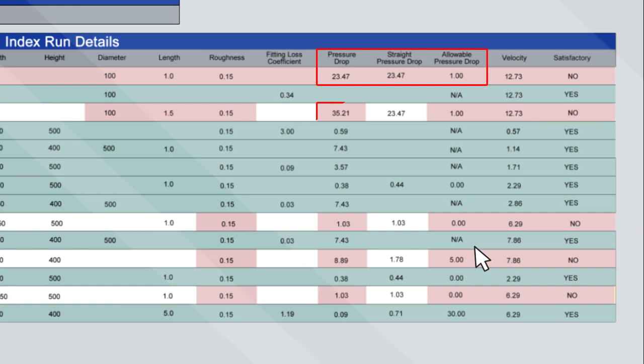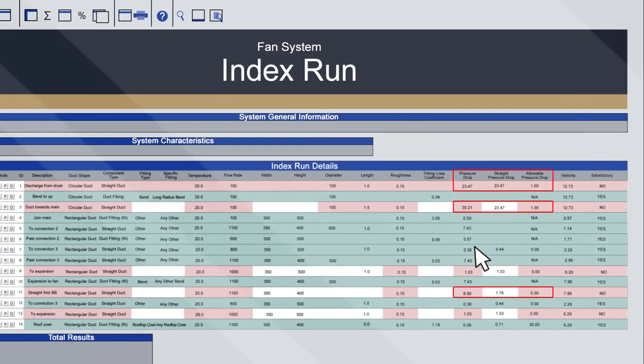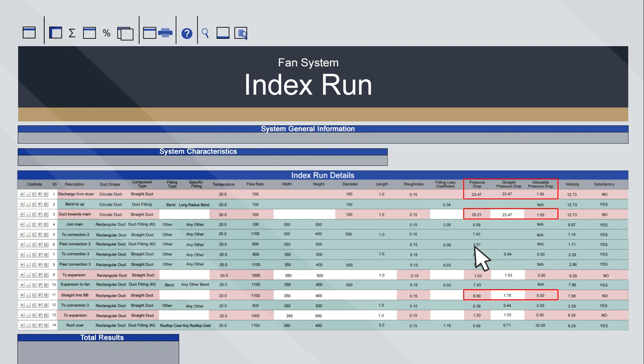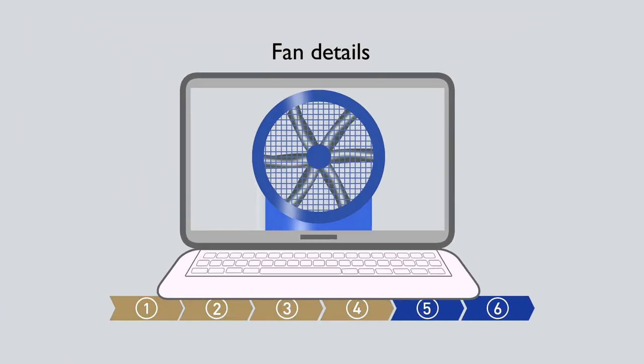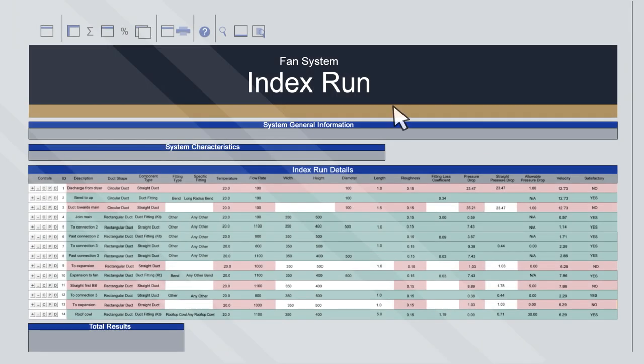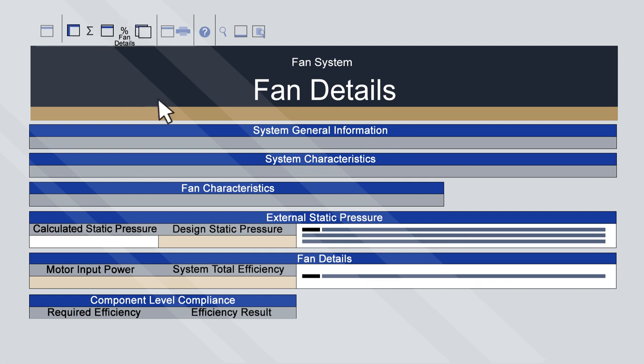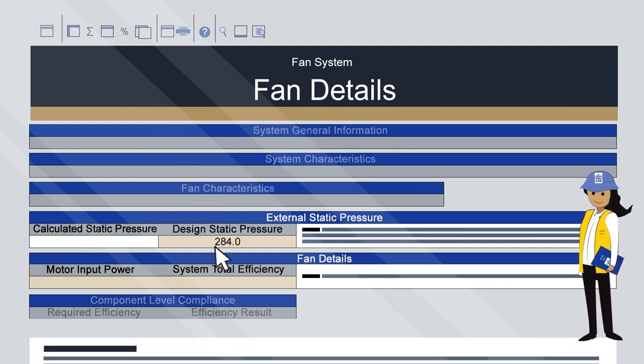There are high pressure drops at the connection to the dryer and in the roof riser section. If these are difficult to change, improving the system's performance in other areas may overcome this efficiency shortfall. Step 4: fan details. Navigate to the Fan Details sheet. On this sheet, enter the design static pressure, motor input power and system total efficiency.